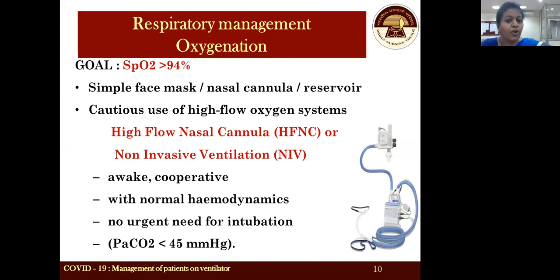Now, the HFNC is quite safe compared to non-invasive ventilation. In the high flow nasal cannula, you can provide a high flow, even up to 60 liters per minute, and you provide heated, humidified air to the patient. The temperature of the air can be increased up to 37 degrees centigrade, and oxygen flow can be given to the patient comfortably without worrying about the patient's safety. This may be associated with less mortality.